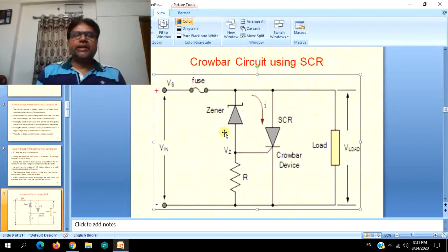After that, some person has to go there and manually check all the circuits, and whenever the supply source becomes normal, this fuse has to be replaced. So this has to be done manually. That is the disadvantage of the crowbar circuit. It cannot regain its position automatically.